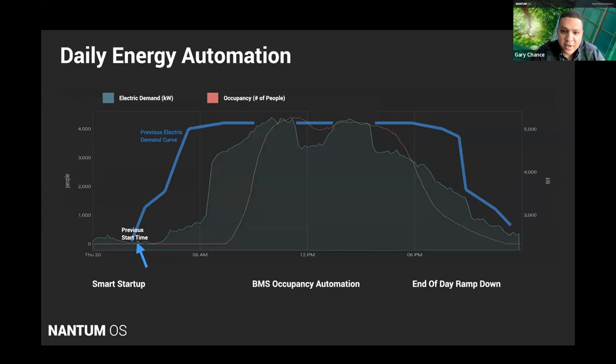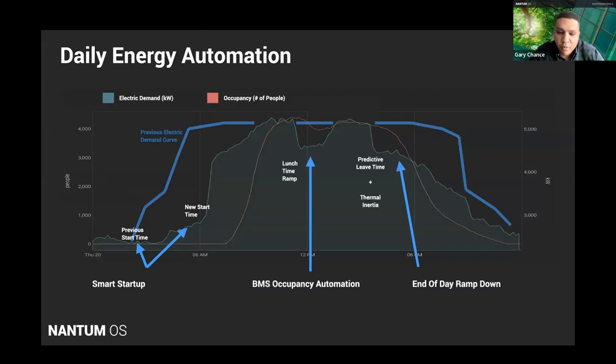Throughout the day you see the previous start time versus the new start time. Beyond that, in the middle of the day we use real-time occupancy and measure real-time comfort to adjust BMS set points, fan speeds, Wi-Fi thermostats, whatever the equipment may be — we're completely agnostic and considered middleware. We're able to use the least amount of energy humanly possible to provide the maximum amount of comfort, all automated in real time.